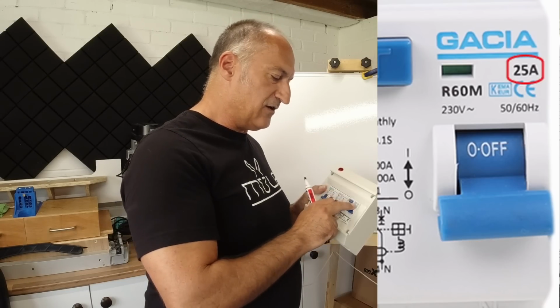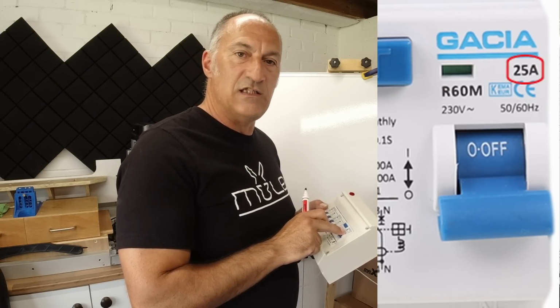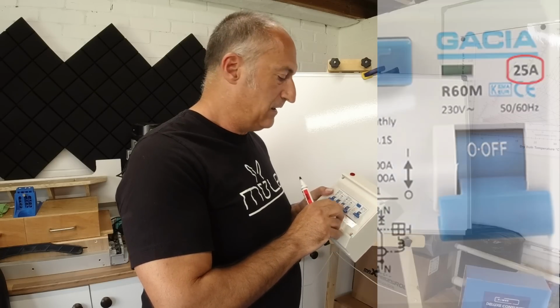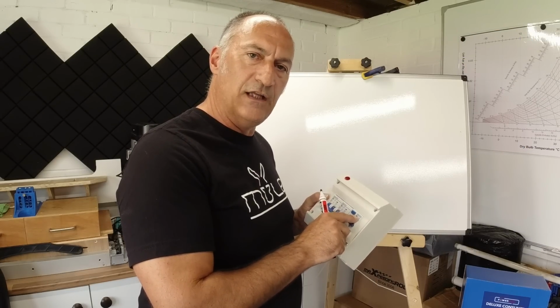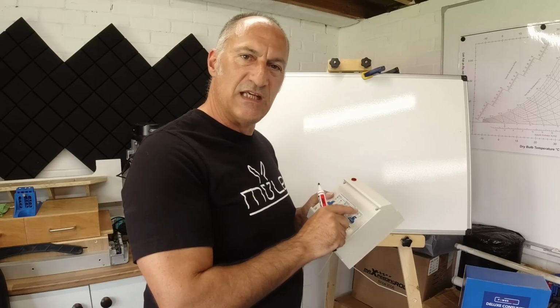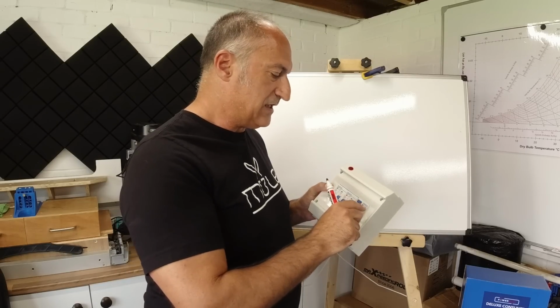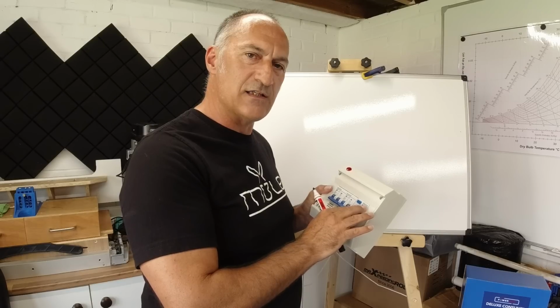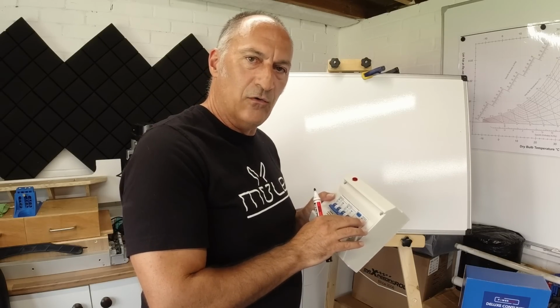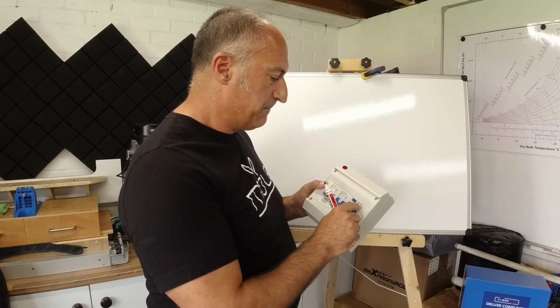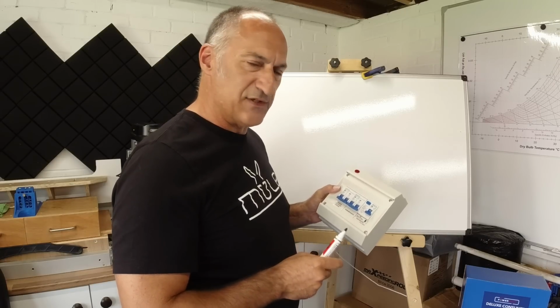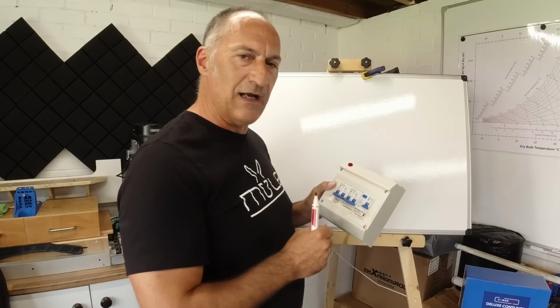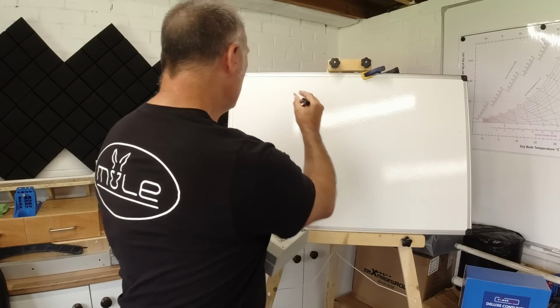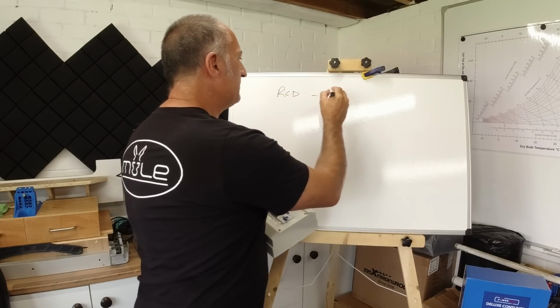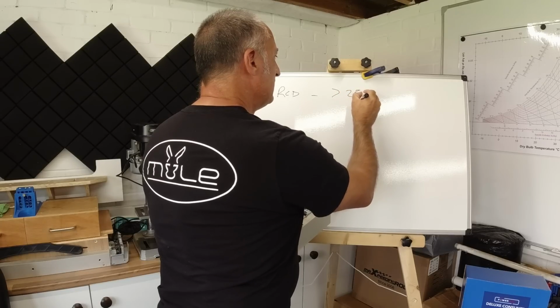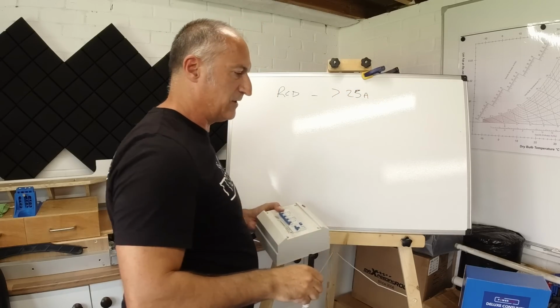So this means that this RCD can handle up to a current of 25 amps on the switch contacts. So there's no real problem with going bigger on this RCD, 40 amp, 63 amp, even 100 amp, because it's just the rating of the contacts within this device. The bigger the rating, the more current it can handle. So potentially it's safer. So as long as that 25 amps is, I would say, a minimum for a camper van. If it's slightly bigger, that's not a problem. So the RCD would need to be greater than 25 amps current rating. That's what you need to look out for.